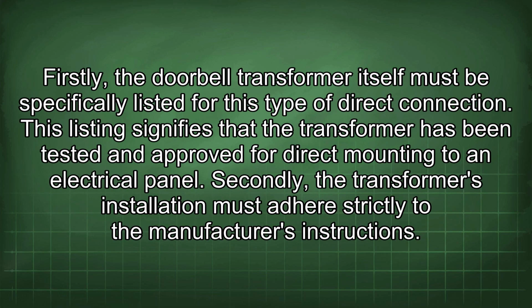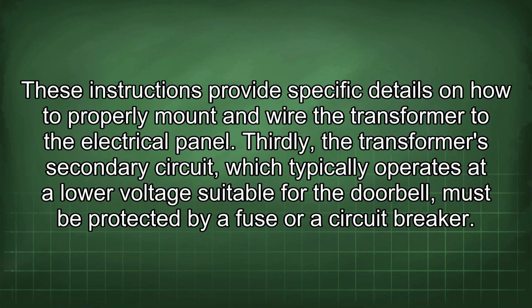Firstly, the doorbell transformer itself must be specifically listed for this type of direct connection. This listing signifies that the transformer has been tested and approved for direct mounting to an electrical panel. Secondly, the transformer's installation must adhere strictly to the manufacturer's instructions. These instructions provide specific details on how to properly mount and wire the transformer to the electrical panel.